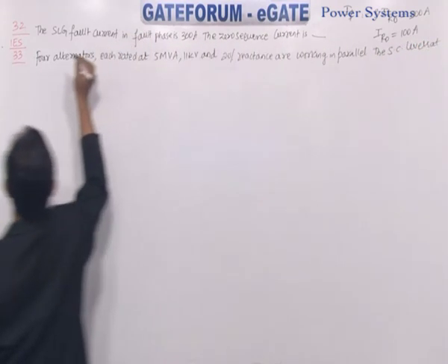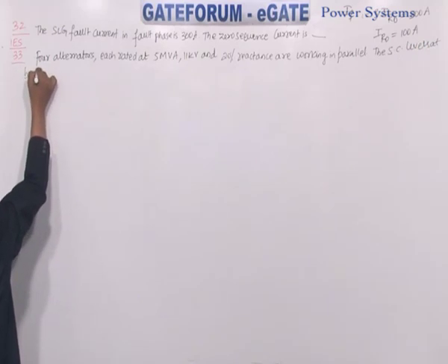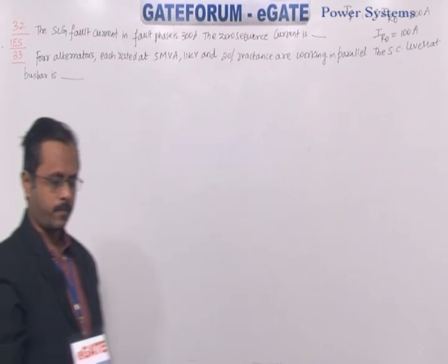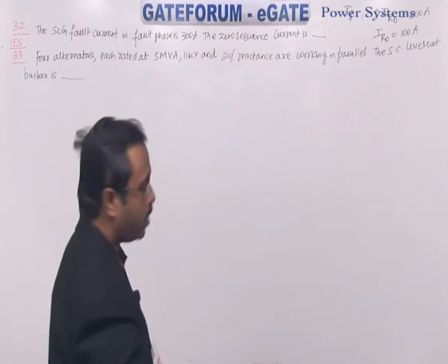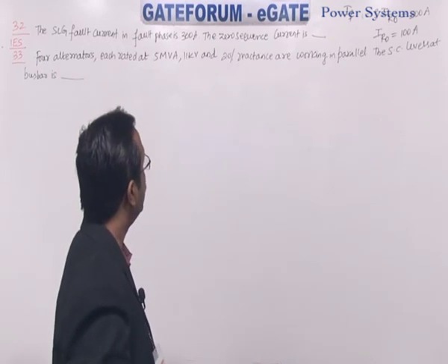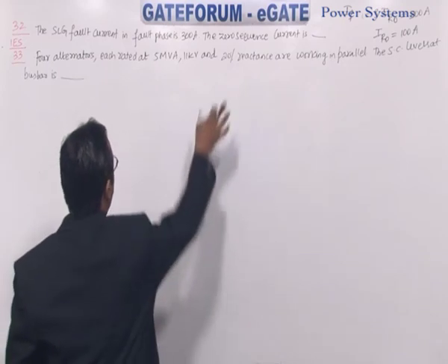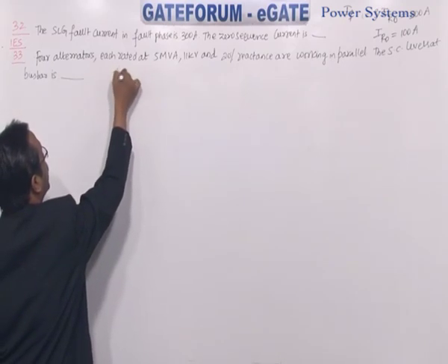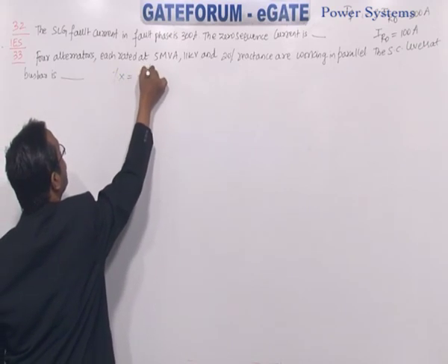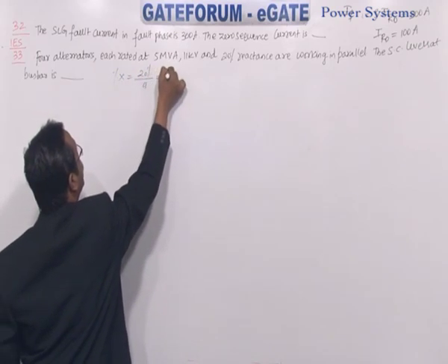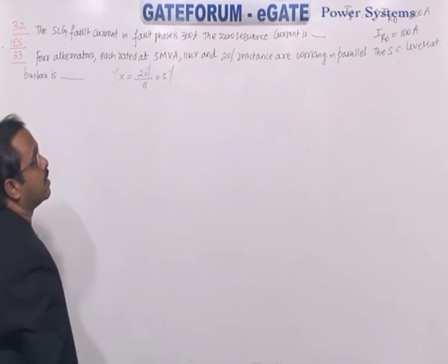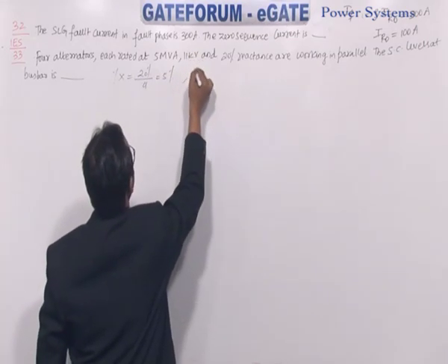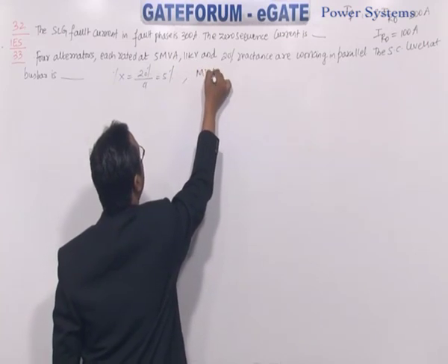The short circuit level at the bus bars. So how to calculate this now? So 4 alternators are in parallel. So what will be the equivalent reactance? 4 in parallel, you get 5%. Then how do you find the short circuit MVA?